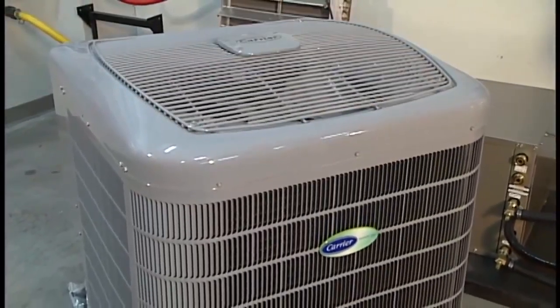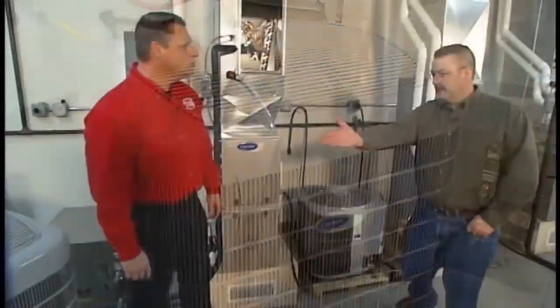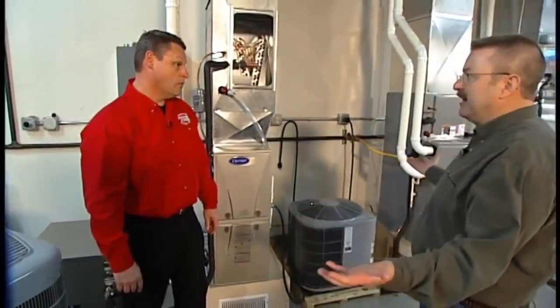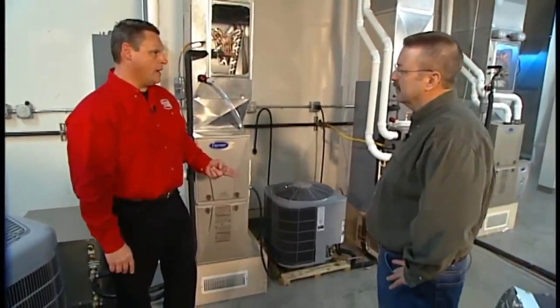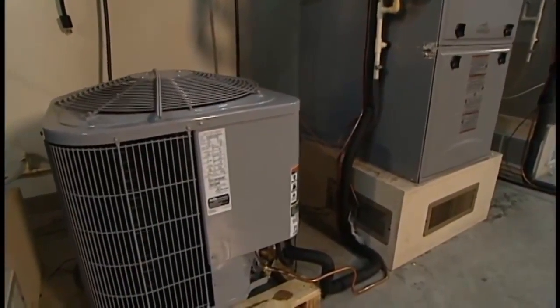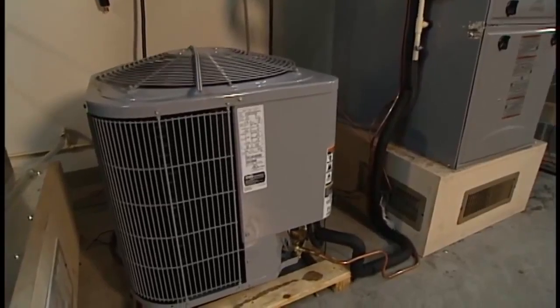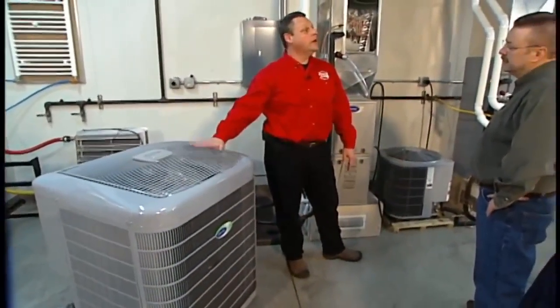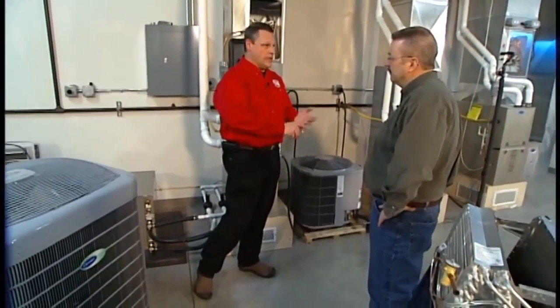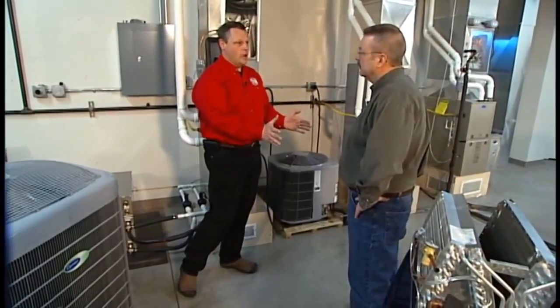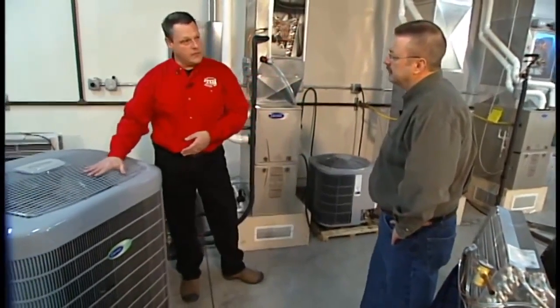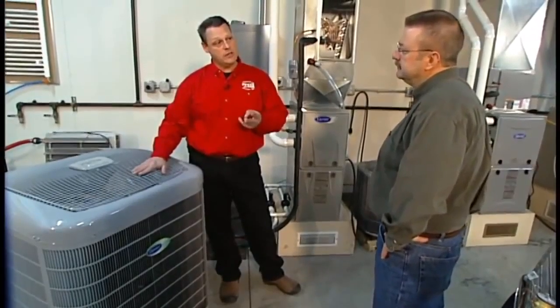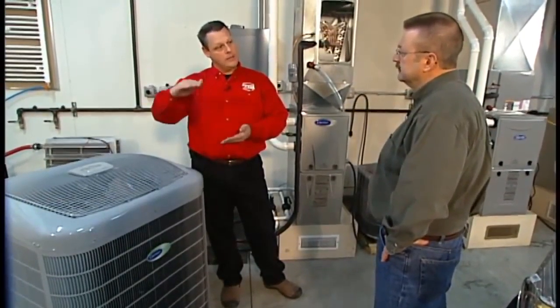Now over here, there's a smaller sized condensing unit as compared to this one here. Is it just based on the size of a house? Two things go into that. These are actually relatively close in the same capacity, but there's a difference in their efficiencies. This is a 13 SEER, this happens to be a 16 SEER. Another thing we have to consider is what we are doing within those cabinetries. This is an entry-level model, so it's going to be an on-off 100% output when it runs. The advantage of this model as well is it brings us two-stage capacity through the compressor. Again, it's an upgraded model.